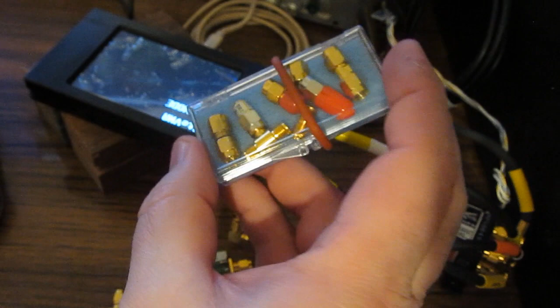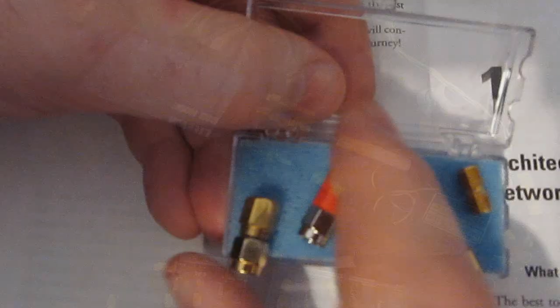Now, of course, we're working at a much higher frequency, so to run through the calibration with these, I have to use the torque wrench. And of course, these have already all been torqued. So let me just go ahead and I'm going to load that calibration. Again, this is looking at our calibration standards that were supplied with the V2Plus4. This is looking at the short, and you'll notice it's been slightly modified. This allows me to use a second wrench to hold that center pin stable while I go ahead and torque it.